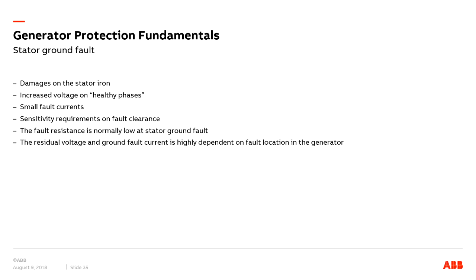So if the ground fault is situated close to the generator terminal, the voltage in the healthy phases will be increased. This gives an increased risk of a second ground fault in another phase. The fault currents caused by the stator ground fault are small as a consequence of the high impedance grounding system. Therefore, a relatively long fault clearance time can be accepted.